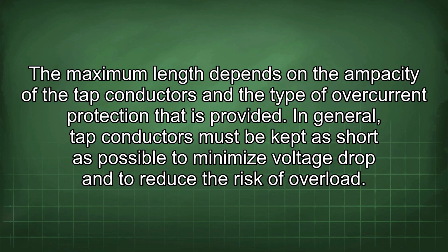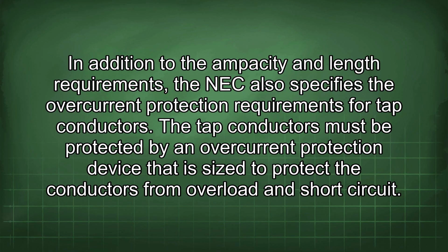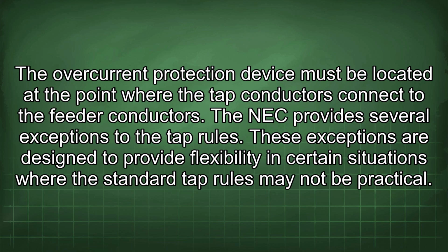of overload. In addition to the ampacity and length requirements, the NEC also specifies the overcurrent protection requirements for tap conductors. The tap conductors must be protected by an overcurrent protection device that is sized to protect the conductors from overload and short circuit.